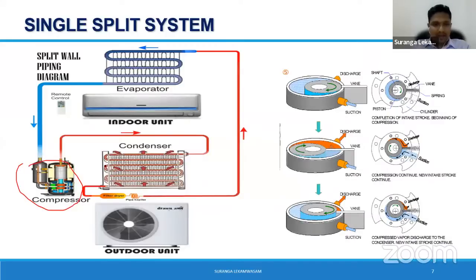When it comes to single split applications, nowadays we are having rotary compressors, right? You can see how the rotary compressor operates. It has an eccentric rotor, which is driven by a motor. So due to the eccentricity, you can do some compression of the refrigerant gas. Then you have the condenser, then the expansion device, which can be a capillary tube or an electronic expansion valve or whatever it is. Then you have your evaporator, known as the indoor unit. Then the cycle continues. So this is the simplest version, which everyone can easily understand.